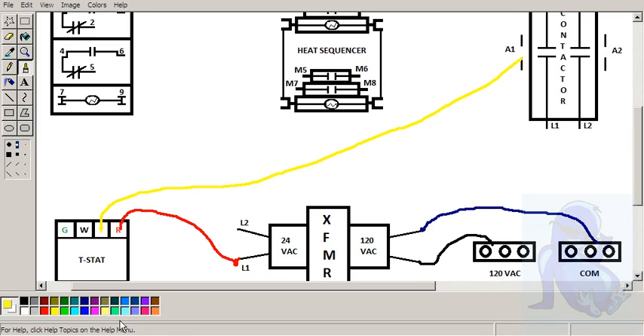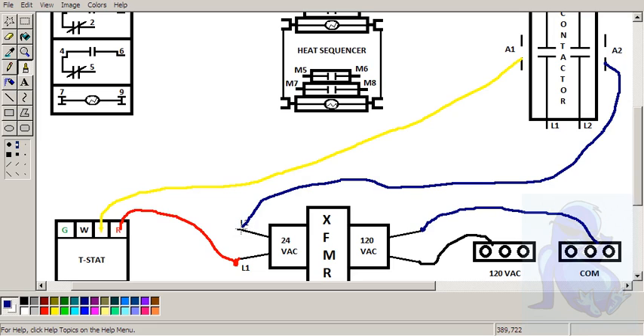and then that is going to come back to L2, and I'm going to let the blue wire, in this case it's actually blue, that's going to come back to L2. So now you've just hooked up a contactor through the thermostat. When you call for cooling, it's going to send a 24 volt to your contactor. It's going to engage that low voltage coil, and it's going to pull that contactor down.